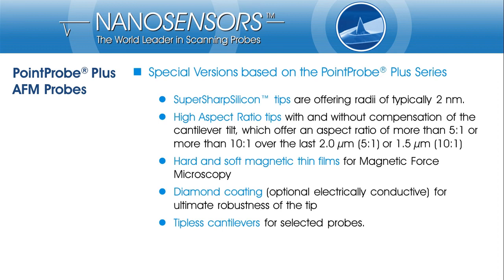Hard or soft magnetic coatings turn PointProbe Plus into probes for magnetic force microscopy. Diamond coatings dramatically increase the wear resistance of the probes and allow applications with high tip-sample forces. As a doped diamond variant, the tip apex is electrically conductive and thus suitable for electrical measurement modes like scanning spreading resistance microscopy.